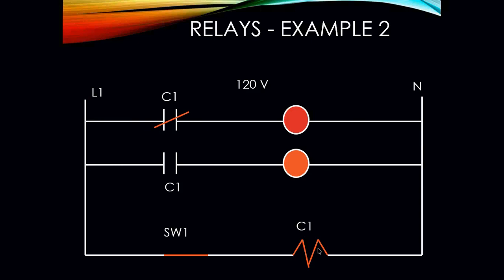However, once I close my switch and I energize my coil, I am now generating that magnetic field. Notice what happened to the contacts. My normally closed has now opened, and my normally open has now closed. So now I have power going through my normally open, and now this load is operating, because I am now generating the magnetic field necessary to make these two contacts change.